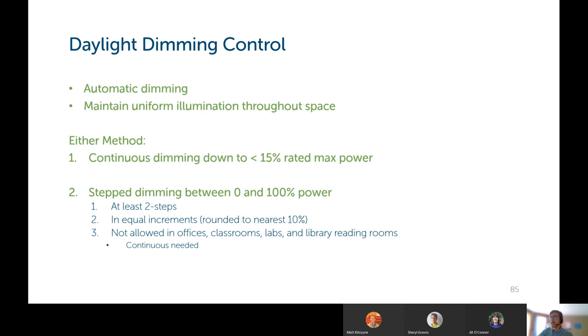More daylight dimming control, automatic dimming, and it should be trying to maintain a uniform illumination level throughout the space. You can do that either with continuous dimming, down to 15% of the max power, and then turn off after that. Or you can do some sort of stepped dimming where you have at least two steps, preferably more, where you're increasing in equal increments, rounded to the nearest 10%, between 0 and 100% power. But that's not allowed in the offices, classrooms, labs, and libraries, where you need the continuous dimming down to 15% and then shut off to 0%.